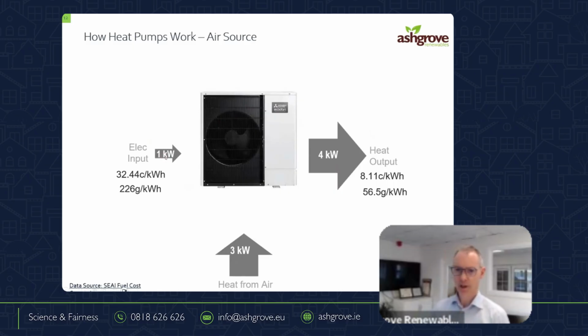If I have an oil boiler and I put in a litre of oil, obviously I get heat going up the flue, I get heat coming out through the jacket of the boiler and so on. So I get 90% of it is usable or 80% of it is usable. In this case, I'm putting in 1 and I'm getting 400% out. Okay. We call that COP. Obviously, if I put in 1 here, I would like 5 out here, or I would like 6 out here, or I would like 10 out here, but I don't want 2 out there, or I don't want 1 out there. Okay? And that's the good news, that's all within our control. So we want that to be as high as possible.